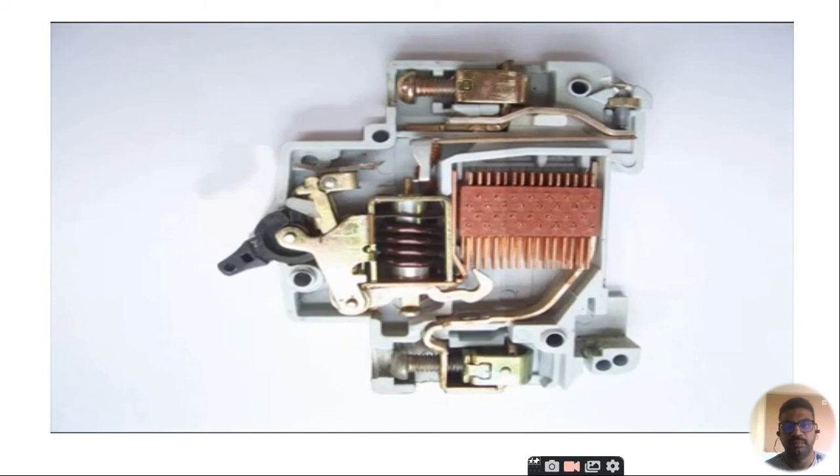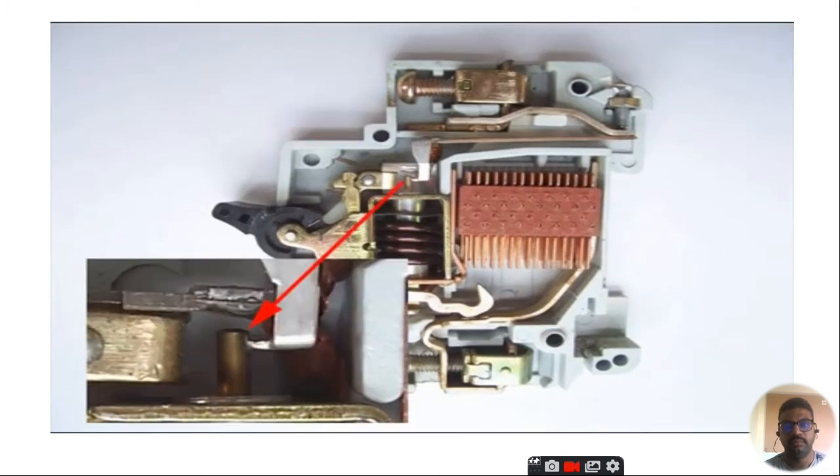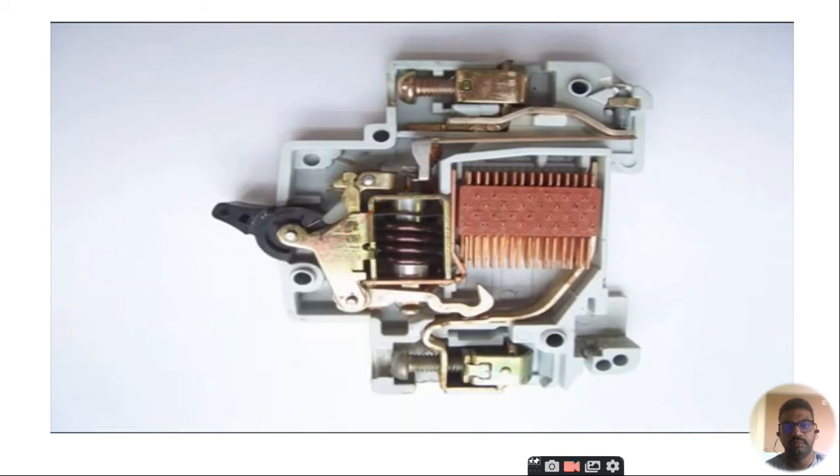The current coil is placed such that during short circuit fault, the MMF of that coil causes its plunger to hit the same latch point and make the latch to be displaced. Hence, during short circuit fault, the MCB will open in the same manner.